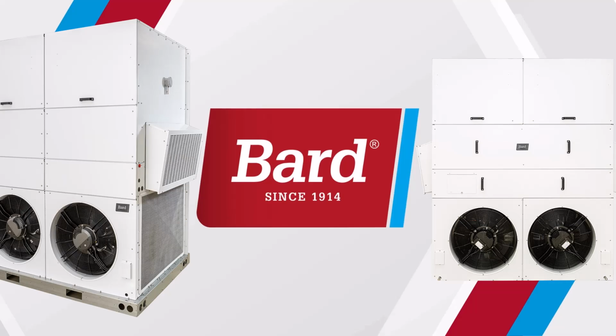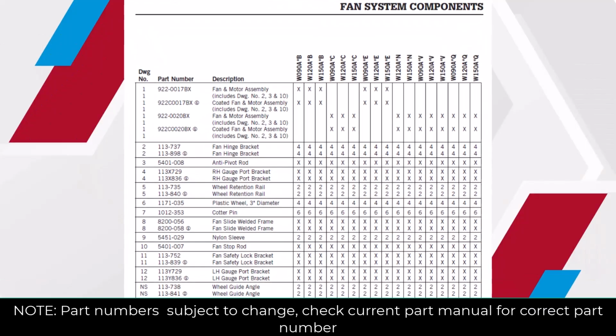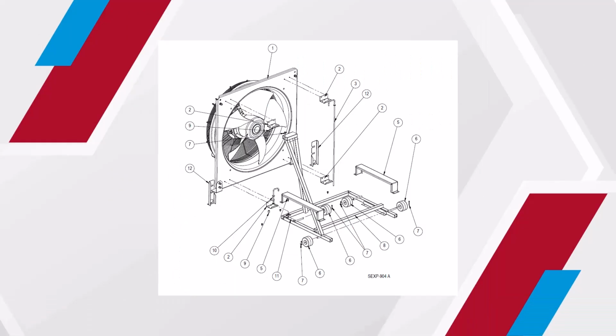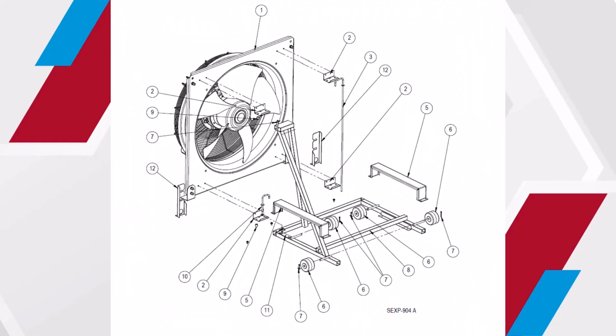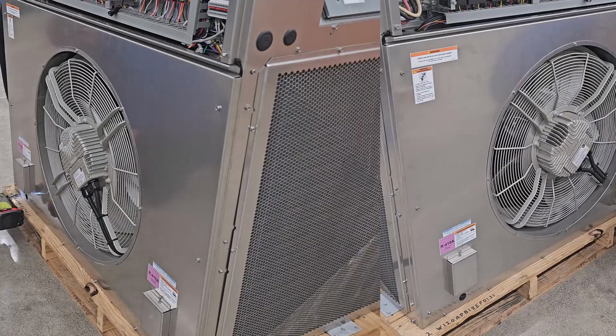We will be removing the power wire and communication wire from the motor and installing a new motor onto the MEGA-TEC. We will then reattach the communication wire and power wire, and perform a function test on the new motor. Turn off power and follow all safety protocols.